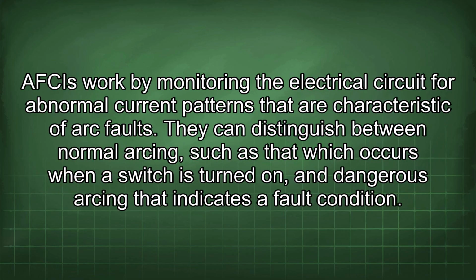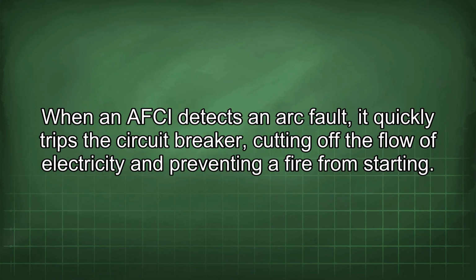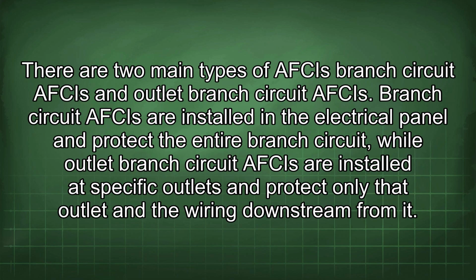AFCIs work by monitoring the electrical circuit for abnormal current patterns that are characteristic of arc faults. They can distinguish between normal arcing, such as that which occurs when a switch is turned on, and dangerous arcing that indicates a fault condition. When an AFCI detects an arc fault, it quickly trips the circuit breaker, cutting off the flow of electricity and preventing a fire from starting. There are two main types of AFCIs: branch circuit AFCIs and outlet branch circuit AFCIs. Branch circuit AFCIs are installed in the electrical panel and protect the entire branch circuit, while outlet branch circuit AFCIs are installed at specific outlets and protect only that outlet and the wiring downstream from it.